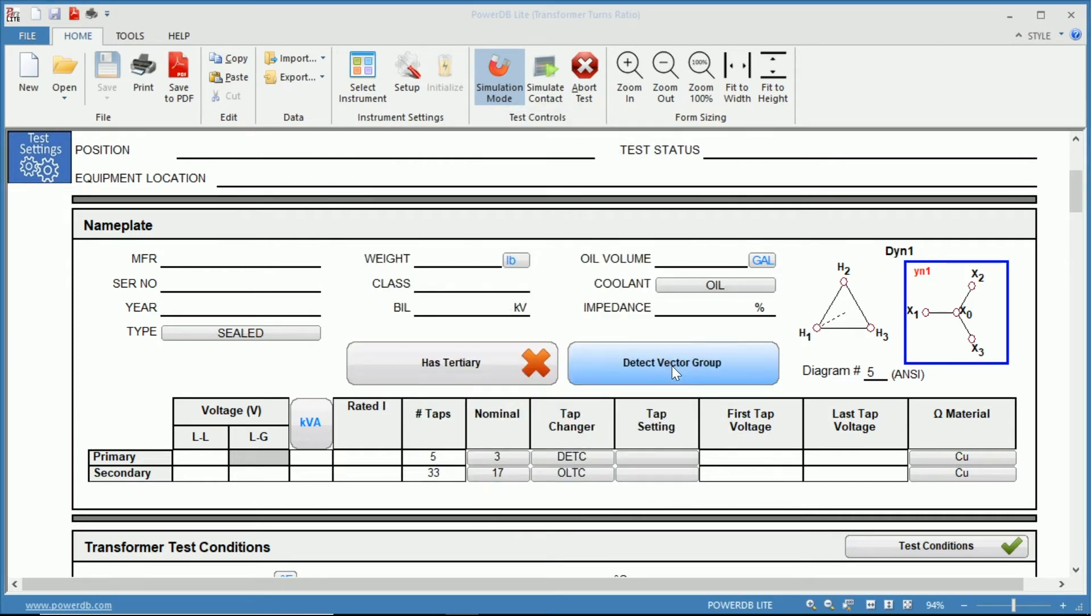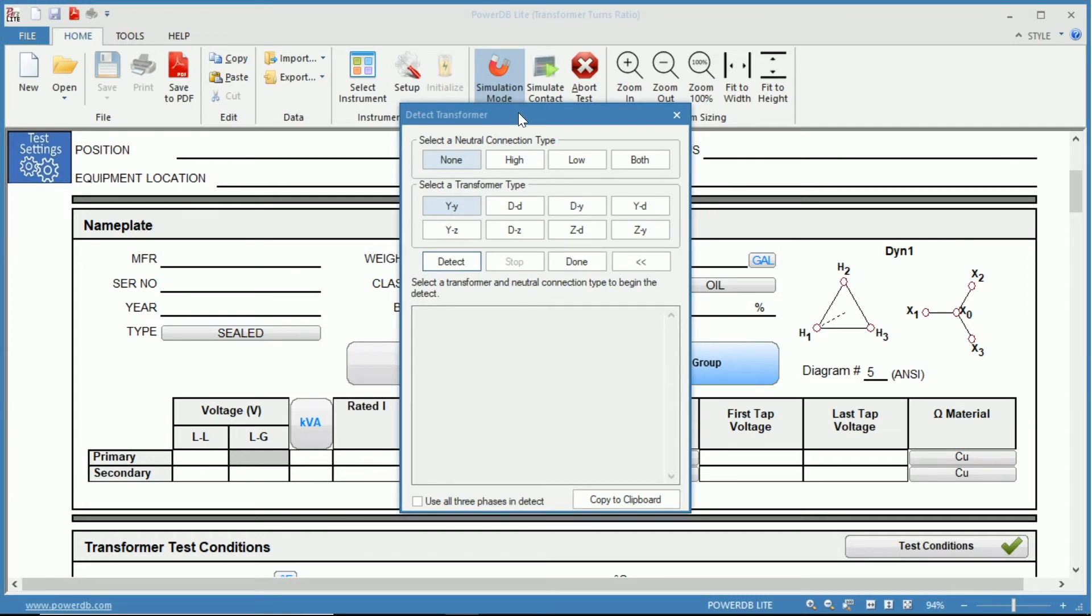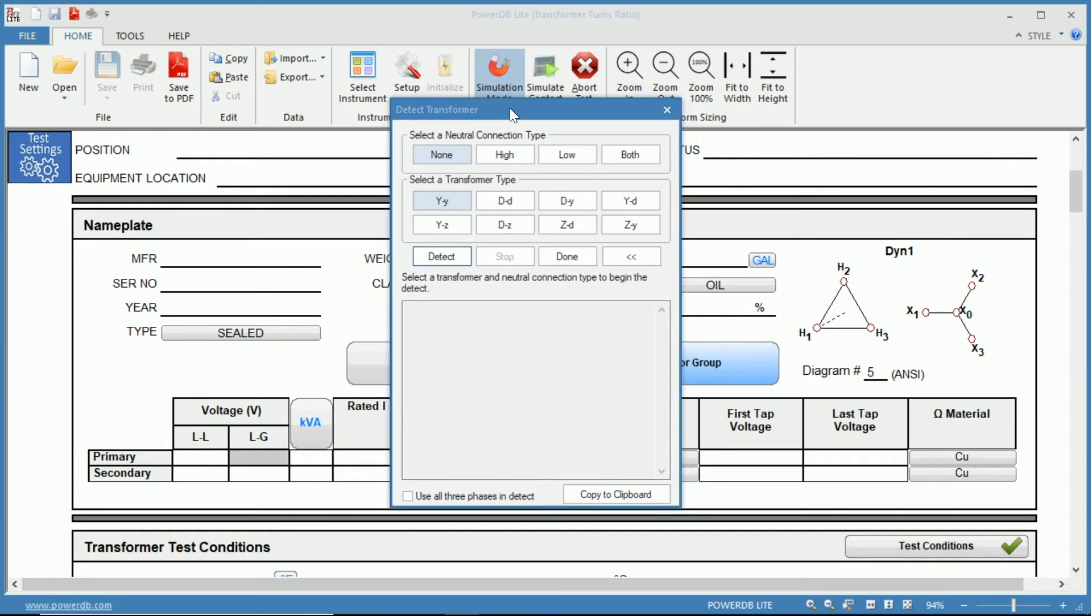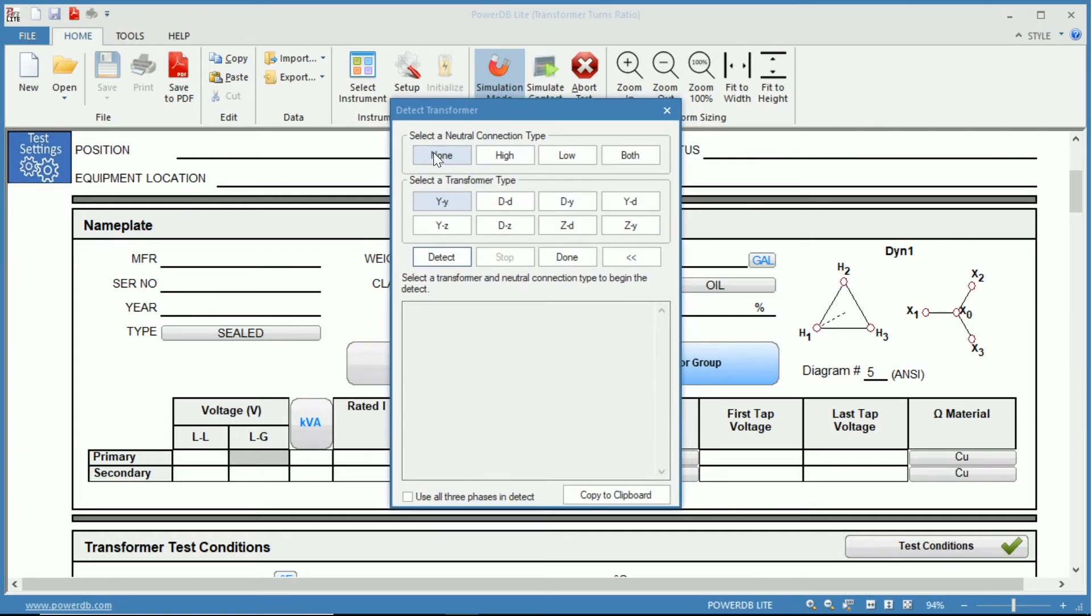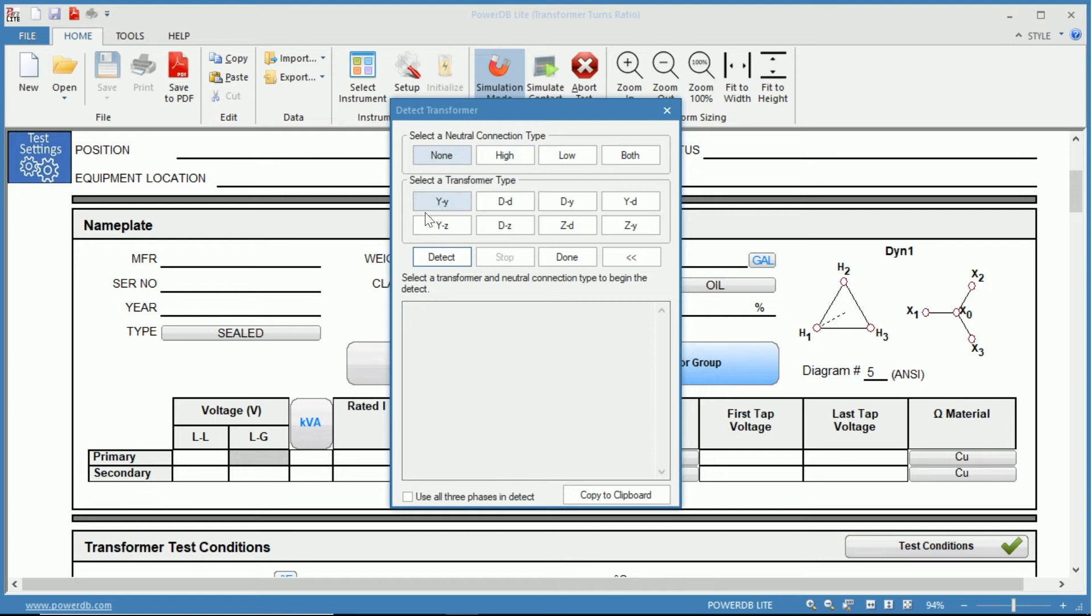So if we open the detect vector group function you can see the first thing we see here is select neutral connection type. So do you have no neutrals, meaning you have a combination of all here? Is it on the high side?